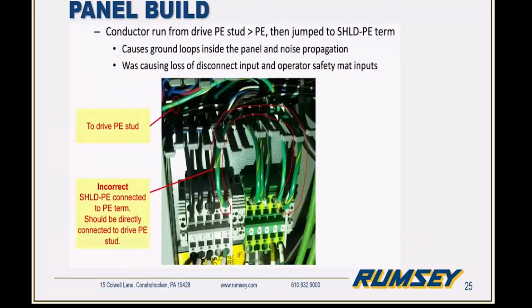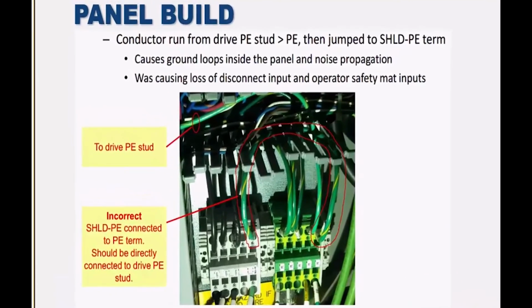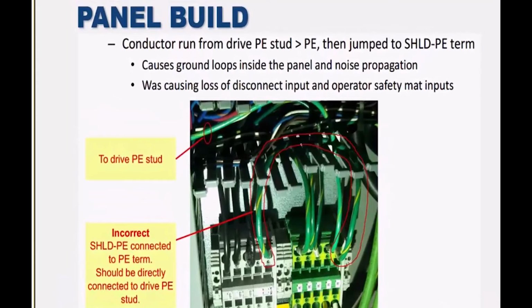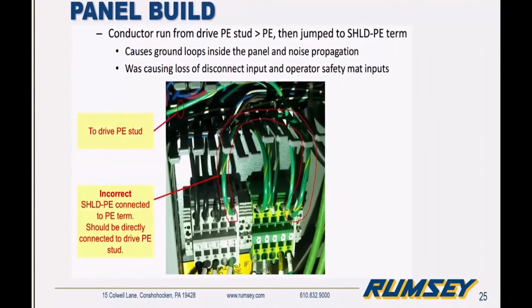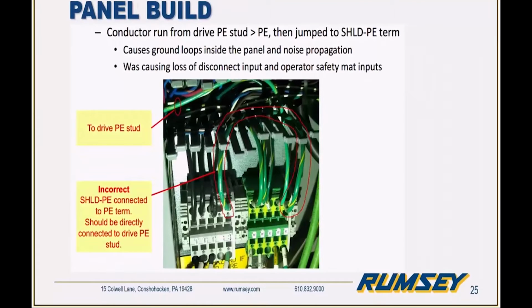So here's an example of improper grounding causing an issue out in the field. We had a motor ground coming back into the panel and tied to the common panel ground before then eventually routing back to the drive. The result was intermittent issues that caused a stoppage on the machine. They were losing the disconnect input and some operator safety mat inputs as a result of the improper grounding here.